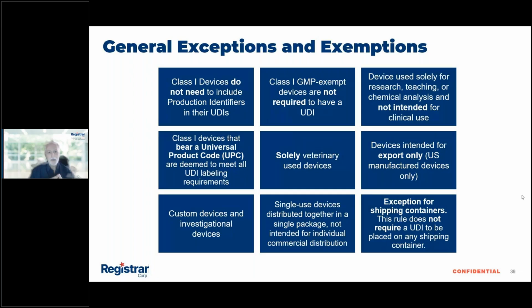Now we are coming to the general exceptions and exemptions. So there's actually a lot, and that makes the whole UDI not really easier. It makes it more complicated, and you have to look into what device I'm really working with and what applies to my device. So as an example, class 1 devices do not need to include a production identifier in their UDIs. Okay, so that means the production identifier is only for class 3 and class 2. I have a class 1, I don't need a production identifier. However, if you want to add a production identifier for your class 1, you can do that, but you don't have to. Regulation does not force you to do it.